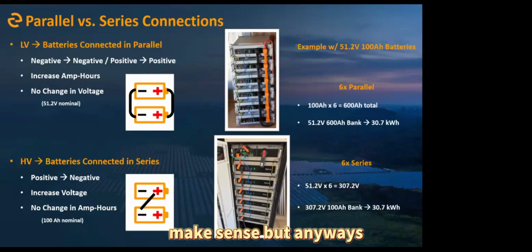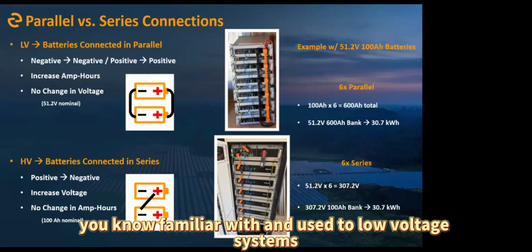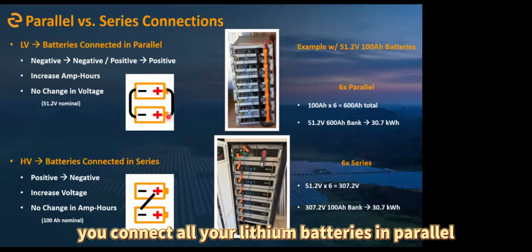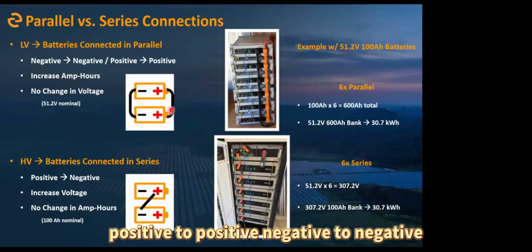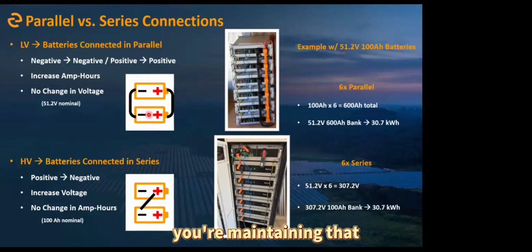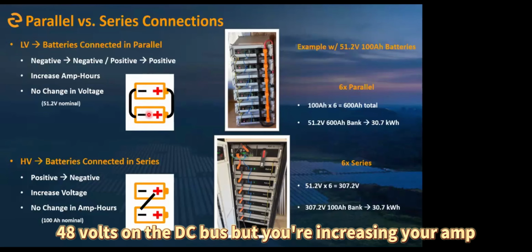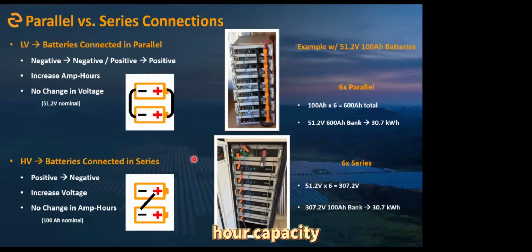What we're all familiar with and used to is low voltage systems, 48-volt systems - you connect all your lithium batteries in parallel, positive to positive, negative to negative. You maintain that 48 volts on the DC bus, but you're increasing your amp hour capacity.